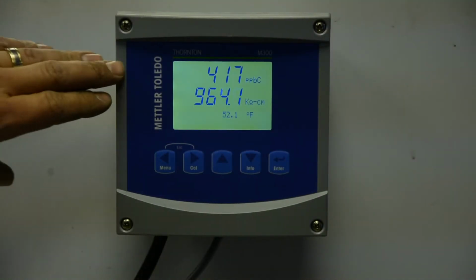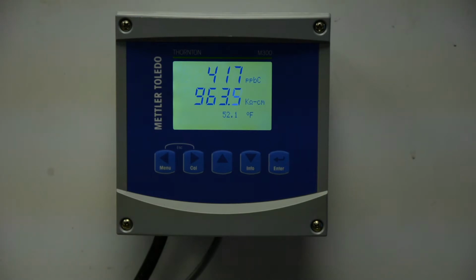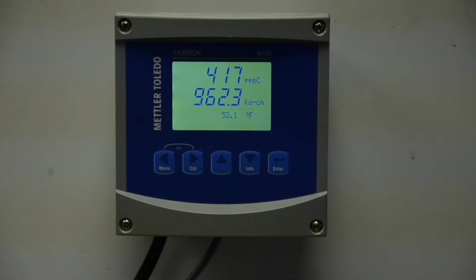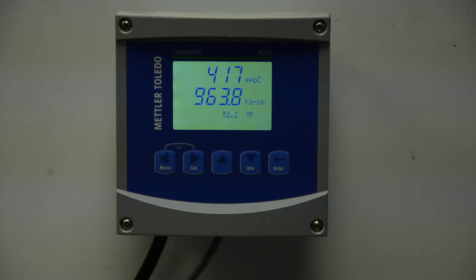Once your solution has stabilized, which this has at 417 parts per billion, write that number down as your as-found data for your TOC. Once you subtract your as-found data from what it's supposed to be, the reference TOC 503, you have a limit of plus or minus 50 parts per billion. Then it asks if adjustment is required, and with this unit, yes, an adjustment is required because it is below. It's at 417 and it should be reading 503 parts per billion.